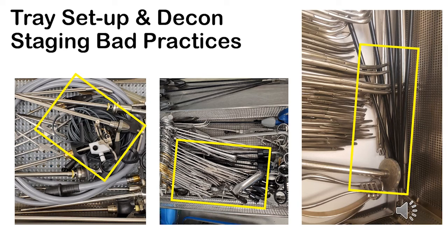In the middle picture, in decontam staging, metal instruments are put on top of the laparoscopic instruments to hold them down, probably because of heavy impingement in the washer. The problem is that those metal instruments are banging against those insulated shafts, cutting and damaging them. The picture on the right is a tray setup, again a prime example of failing to separate your metal instruments from your insulated instruments, where you can see the tips of those metal instruments scraping against those insulated shafts.